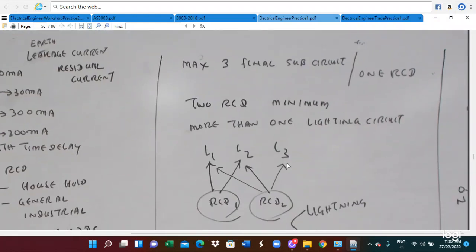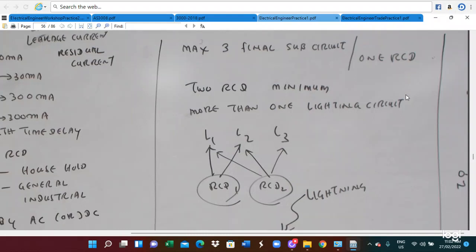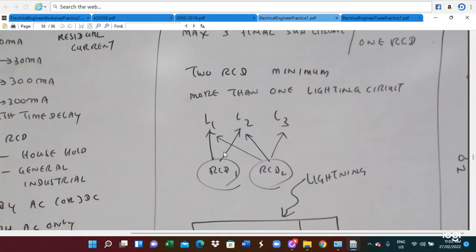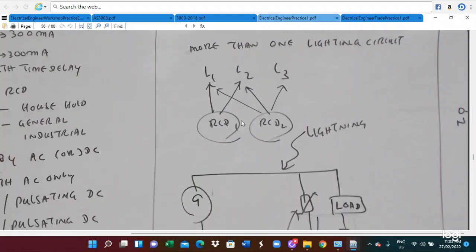One RCD can protect a maximum of three final sub-circuits. If there are more than three final sub-circuits, another RCD must be arranged. If there is more than one lighting circuit, two RCDs must be used. The lighting circuits are arranged so that circuits L1 and L2 are connected to RCD1, and circuits L2 and L3 are connected to RCD2.